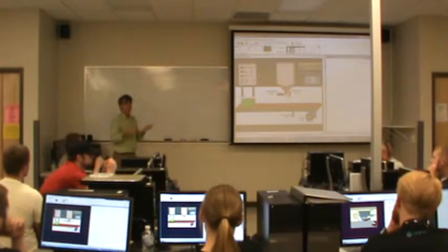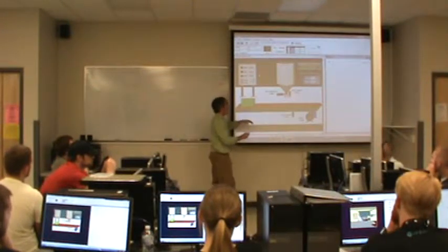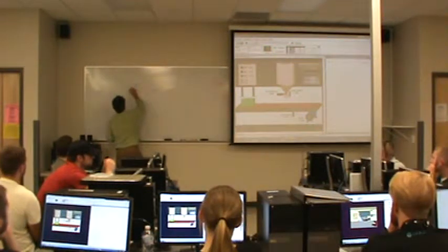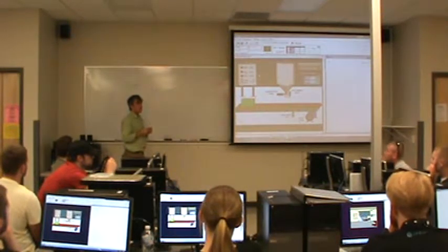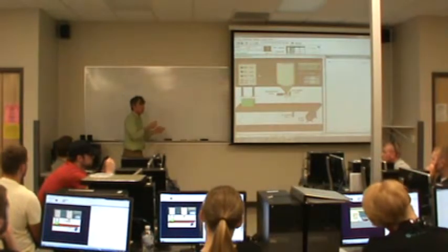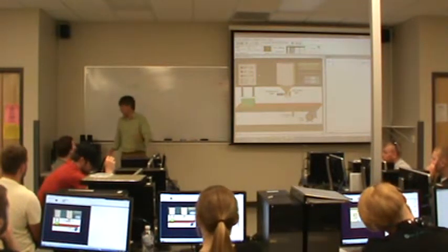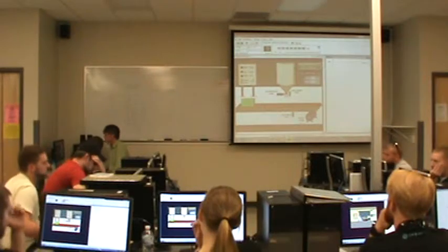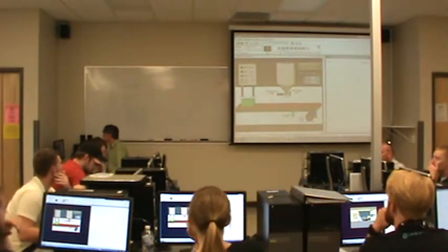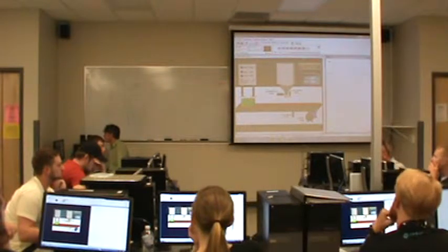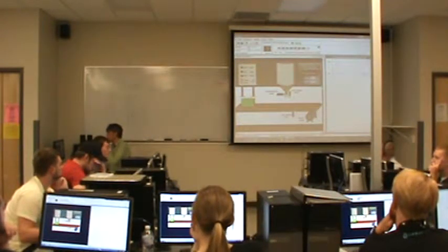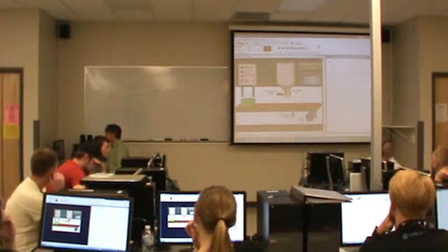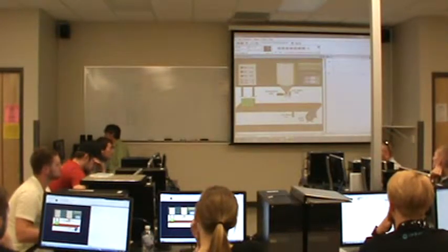Okay? Really, the start and stop button don't start and stop the motor, they start and stop the system. So how about instead of using truth table programming for the start and stop button, we just do what we've already done and use a seal-in? We're going to use a little bit of glue code, or advanced programming, but then we're going to use truth tables for the rest of it. So what I'm going to do is create a seal-in circuit, not based on the motor, but based on the run lamp. Because the run lamp basically just indicates when the system is on, not when the motor's running, right? So I'm going to use an output that is the run lamp.